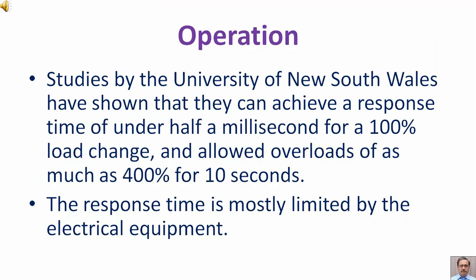Operation: studies by the University of New South Wales have shown that these batteries can achieve a response time of under half a millisecond for a 100% load change, and allow overloads of as much as 400% for 10 seconds. The response time is mostly limited by the electrical equipment.